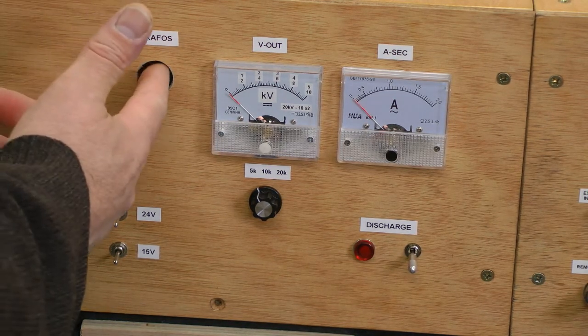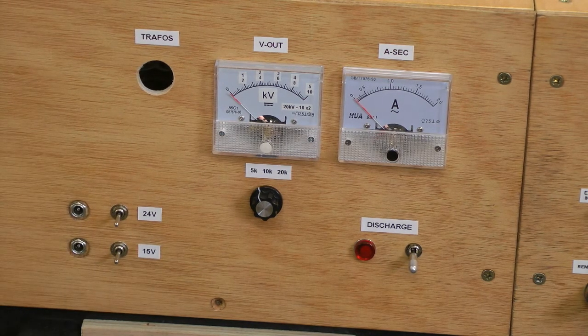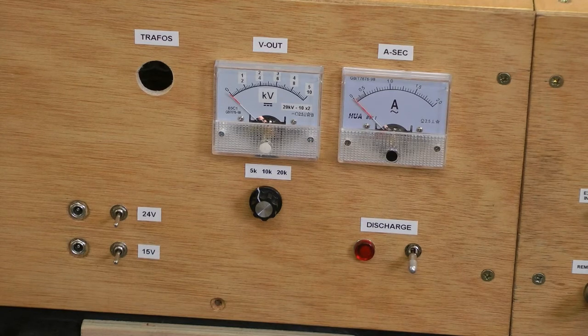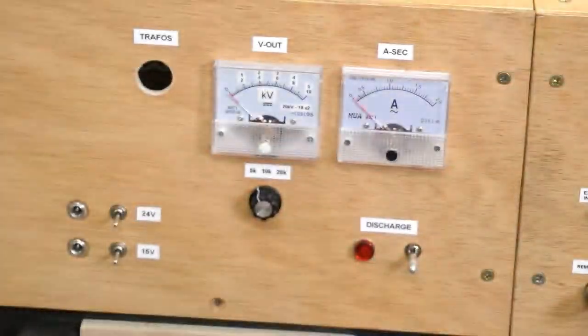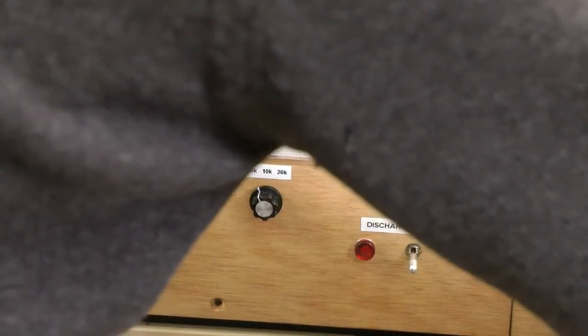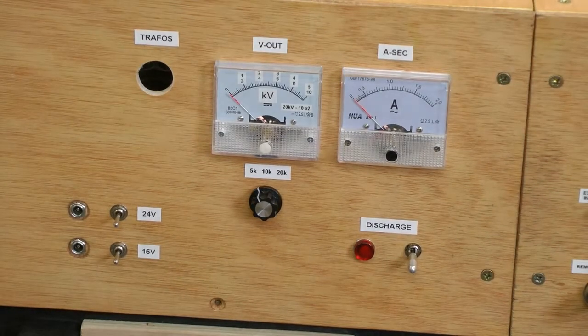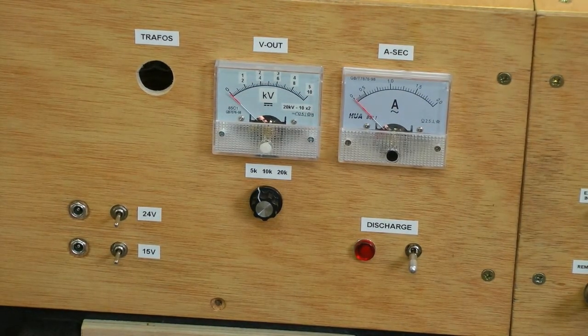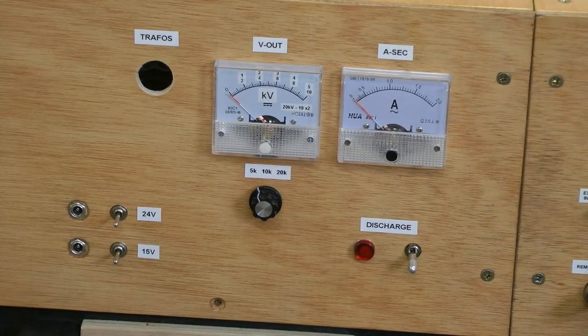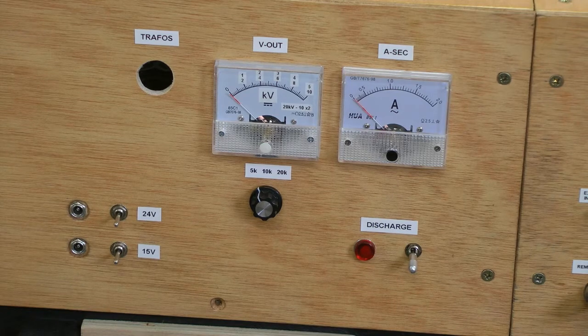You then have a bulb here, which on the inside is a normal incandescent bulb which illuminates when there's power applied to the transformers. That will light at the final stage, before these switches. It shows that there is power coming to the 3 transformer switches. If you have those transformer switches off, then obviously there is power available, but there's actually going to be no power on the transformers. As soon as you've got some of these switches on, if this is lit, then those transformers are going to be fed power. So it's a final safety or warning light, and it shines quite brightly when it comes up, and you can see the illumination from the side. It's a good indication that the system is powered.